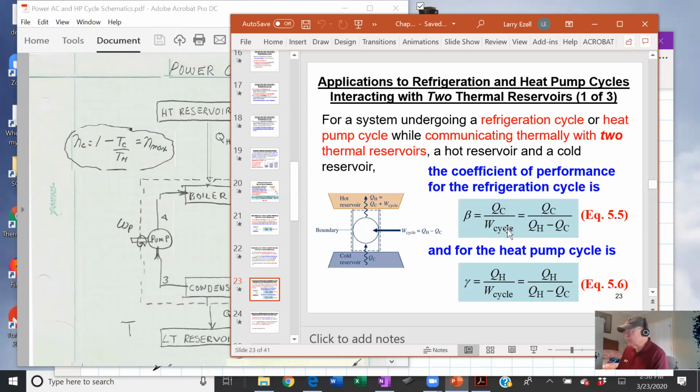And most always, this work energy is electrical energy into an electric motor to drive the compressor. There are also other smaller motors in the air conditioning system, such as fan motors. There's two or three fan motors that run, but these consume less than a horsepower all added together, whereas the compressor may be consuming 20, 30, 40, 50 horsepower.